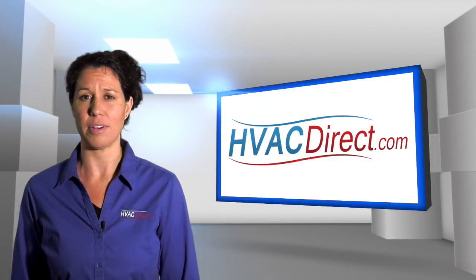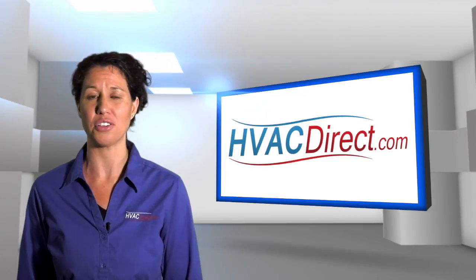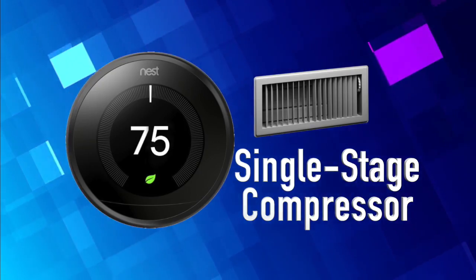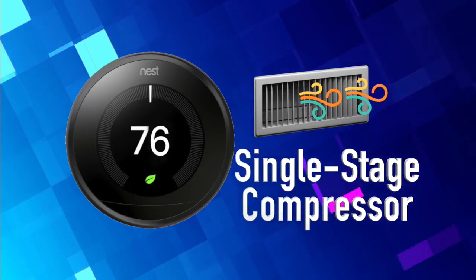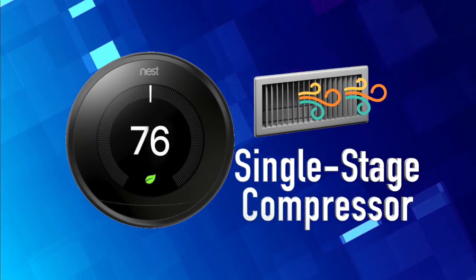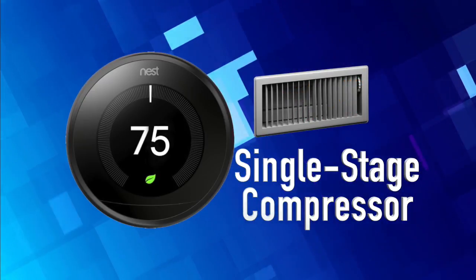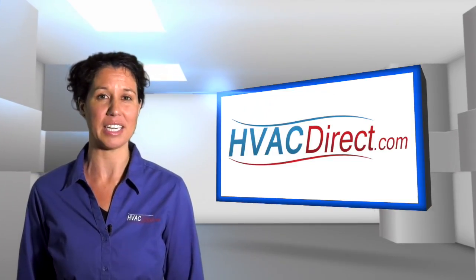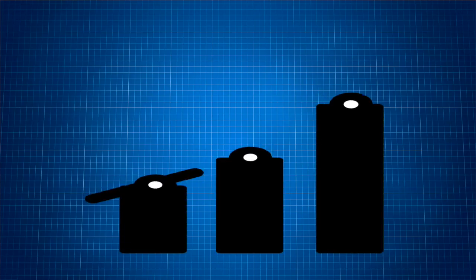A single stage compressor turns on when indoor temperatures exceed the temperature setting on your thermostat. For example, if you set the thermostat to 75 degrees, the air conditioner will run anytime the indoor temperature hits 76 degrees. After the AC cools the house back to 75 degrees, it will turn off again. Single stage compressors always operate at 100% capacity. They turn themselves on and off continuously throughout the day.